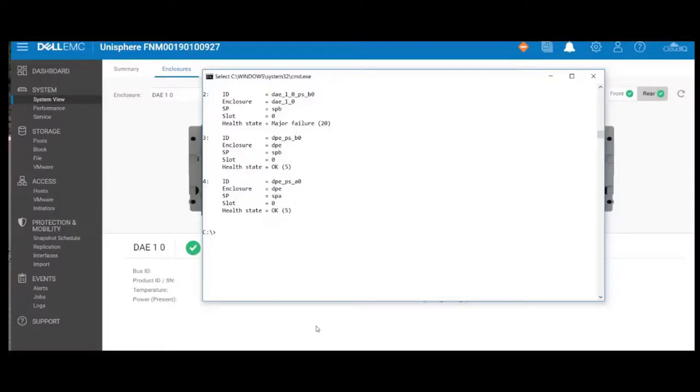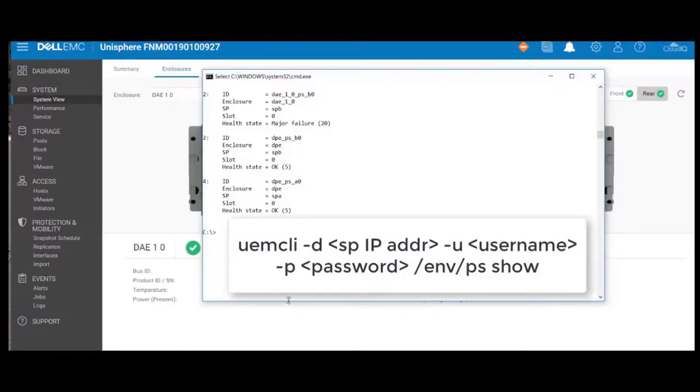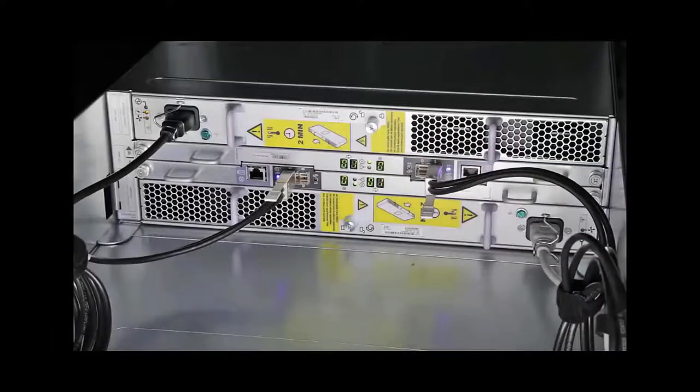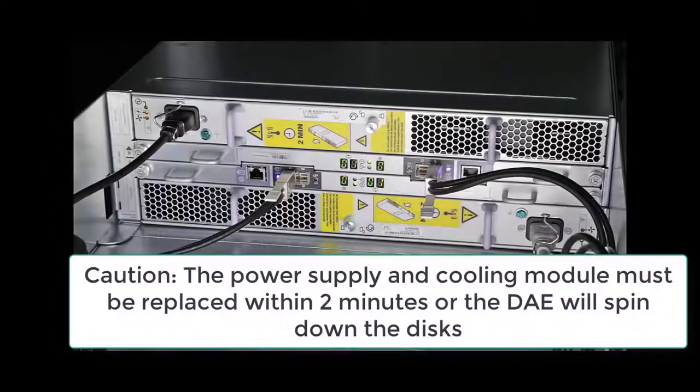And then finally, with the UEMCLI, I can go ahead and see that I have a failure on that supply. It's DAE 1, 0, power supply B0, and you can do that with the ENV PS show command.